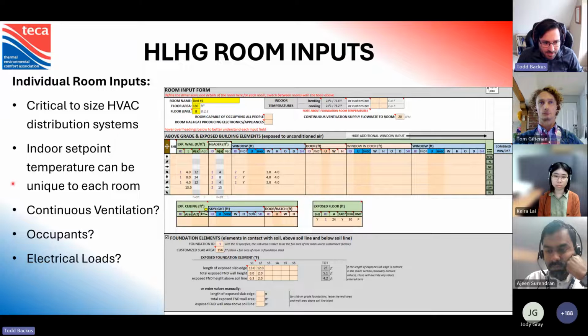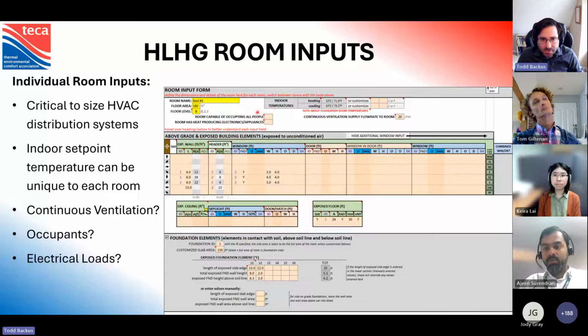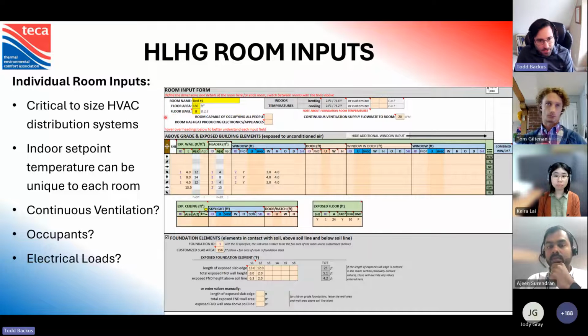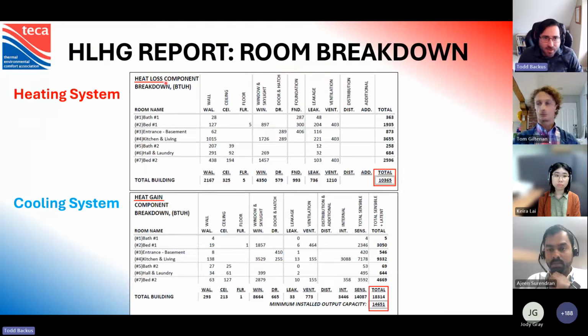There are a couple of other things that you need to be mindful of. Is there continuous ventilation in this room? Are there occupants? Are there very high electrical loads? All these things you end up just entering into the calculator, and then they show up on the reports side. So this is a breakdown of the components. Here we have the heat loss component breakdown in BTUs per hour. This is how you size your heating system. Below we have the heat gain component breakdown. This is how you size the cooling system.